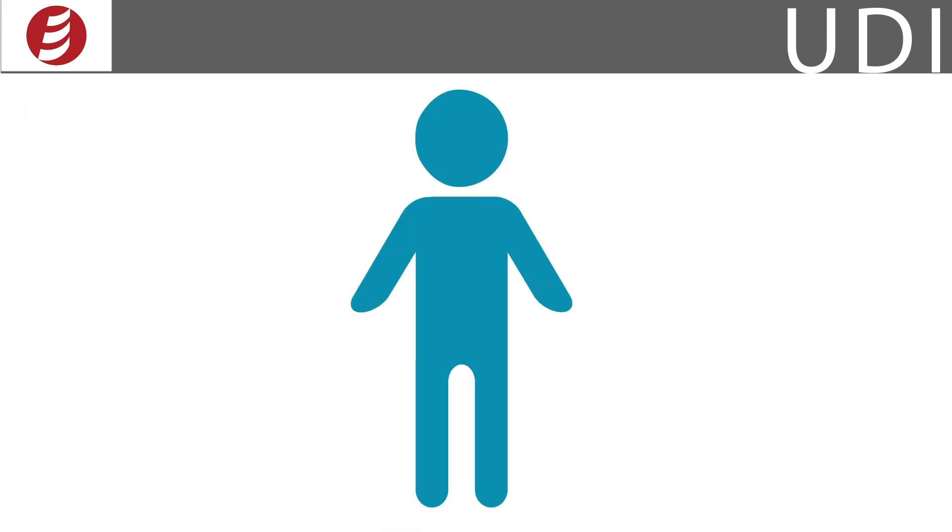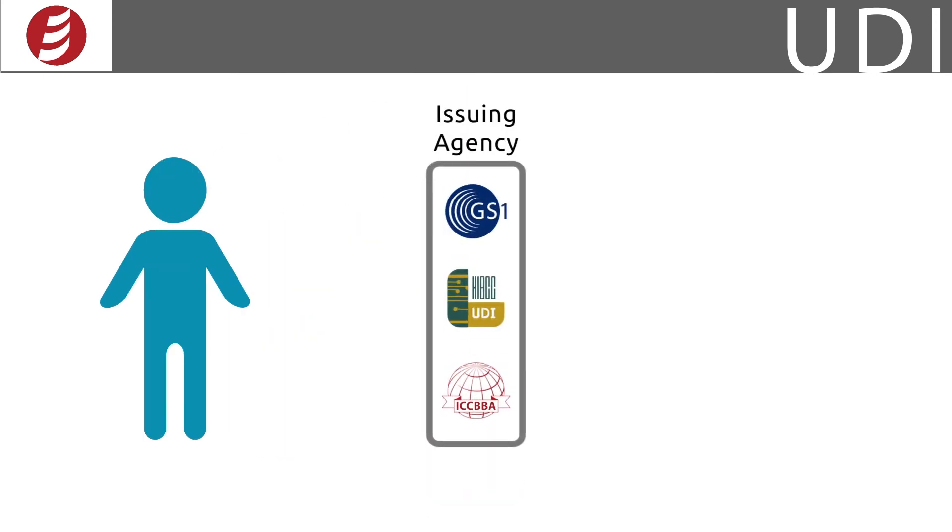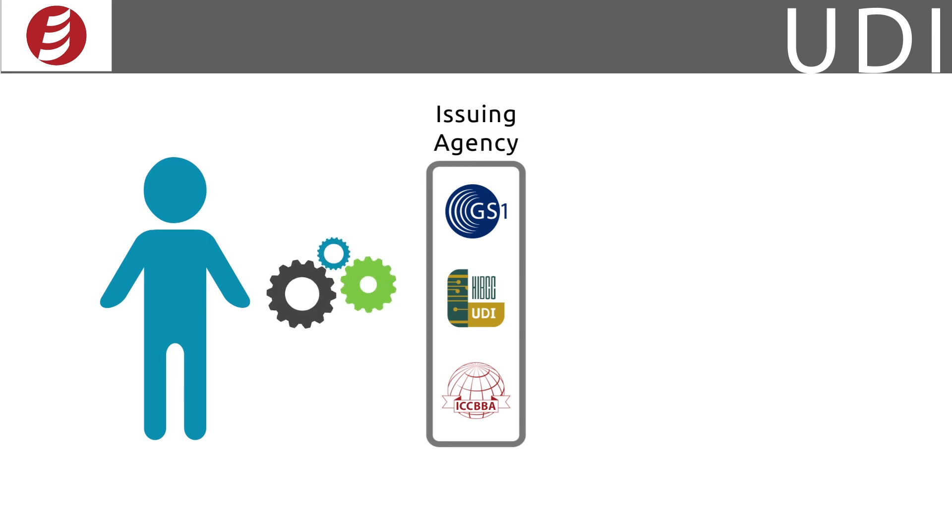As mentioned earlier, you obtain your DI from an issuing agency which identifies the labeler and the specific version or model of the device. Select which IA you want, pay their fees, and submit your product and manufacturer information to them. They, in turn, supply you with a DI.